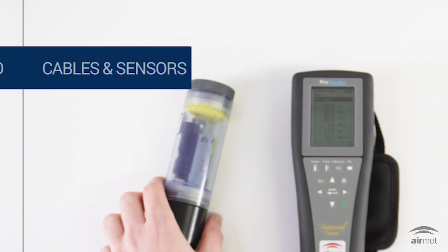Now let's take a look at the cables and sensors. The ProQuatro has a 4-sensor sonde allowing for the device to measure pH, temperature, conductivity, dissolved oxygen, and oxidation reduction potential simultaneously. The YSI ProQuatro can record up to 5,000 data points and record in interval or single event logging mode. The device has user-adjustable auto-stabilization with prompts.